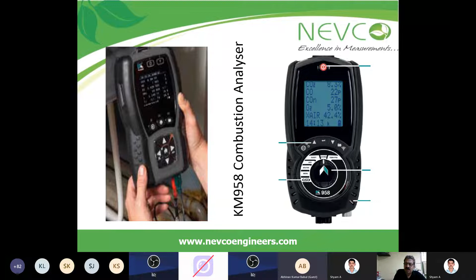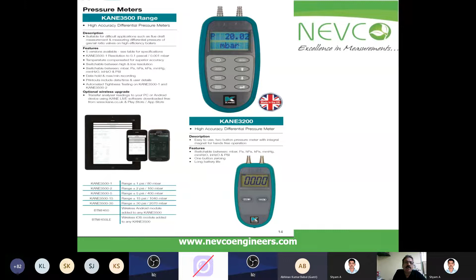It looks like this, the 958 combustion analyzer. This is very widely used because it is a low-cost model. And then we go to pressure. We have Kane, UK make, different types of pressure meters. You can measure positive pressure and differential pressure with a pitot tube.